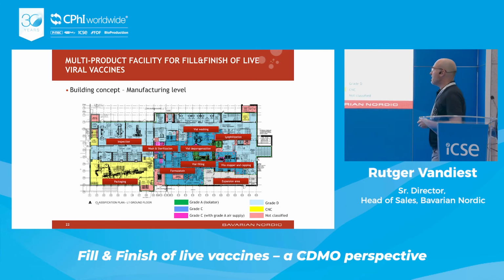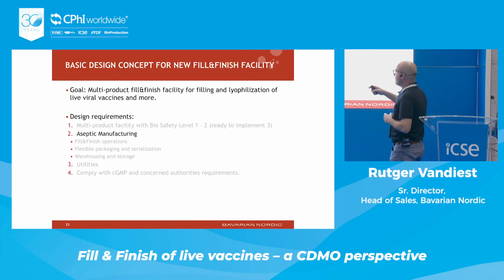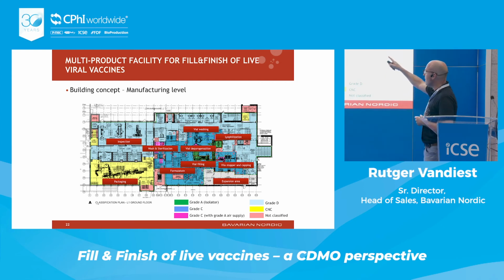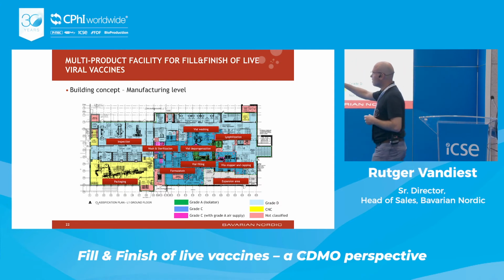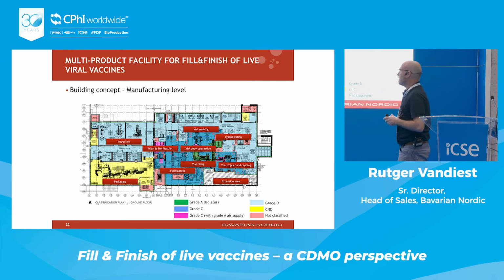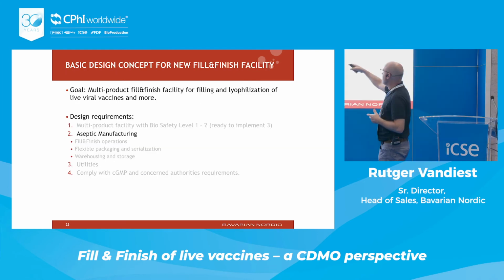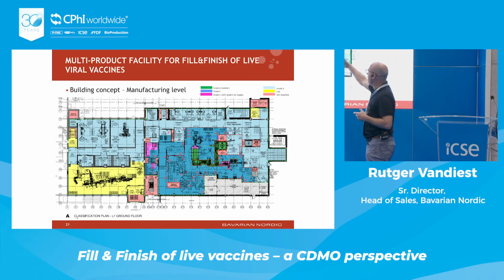We have our washing and sterilization area, where we do the washing and sterilization of the utensils. We have vial washing, depyrogenation, and the vial filling. This is all in the isolator. If it's a lyophilized product, we can go to the freeze dryer and bring it down to vial stoppering and capping. Afterwards, we can go to the storage area, which is in between inspection and packaging. It can go to inspection and packaging, and it can go out through specific killing autoclaves. If it is a diluent, for instance, we can pass it after filling through a terminal sterilization autoclave.